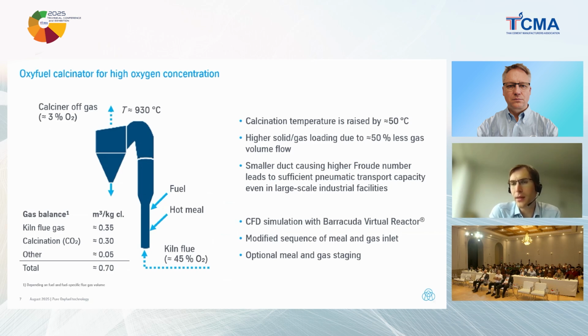In the development phase, this also has been intensively investigated by the Barracuda virtual reactor CFD package, which is capable of simulating entrained flow reactions. There's also the principle to first add some hot meal and after that the fuel into the calciner, because ignition is no longer an issue, but it shall be ensured that there is some hot meal, some calcium carbonate in the gas stream to absorb the heat from the combustion as soon as that takes place. And like some plants already have today, there is the option to do some meal and gas staging, a meal and fuel staging to improve the combustion and maintain a sound temperature profile in the calciner. So these are two major aspects how the kiln line can be operated while feeding the high concentrated oxygen to the clinker cooler.